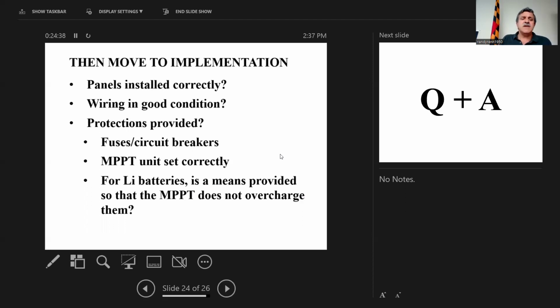Are there fuses and circuit breakers in proper locations? We always fuse the outputs of the MPPTs, not because the MPPTs can source a lot of fault current - they can't - but the battery can, so it's more to protect the unit than the battery. And then, did somebody go through and set up the MPPT correctly?